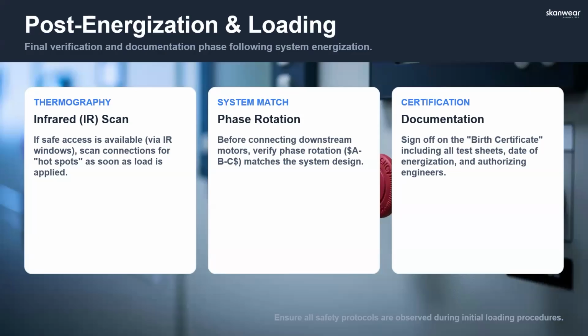Yeah, just in addition, as we talked about earlier, there's the use of partial discharge testing as well. Whether it's on first energization or post maintenance, where we've taken it out of normal operation, made modifications and then re-energized. Infrared's great, and all the other bits are brilliant as well. Partial discharge testing gives us, as engineers, a whole different raft of information that we can use to identify minor faults, poor terminations, poor joints, things like that. So, as an additional thing, maybe throw that in there as well. Good practice.